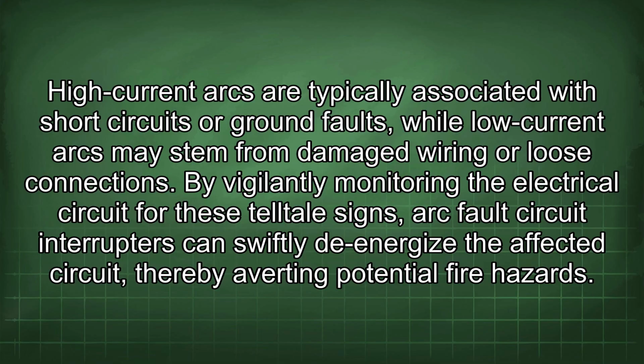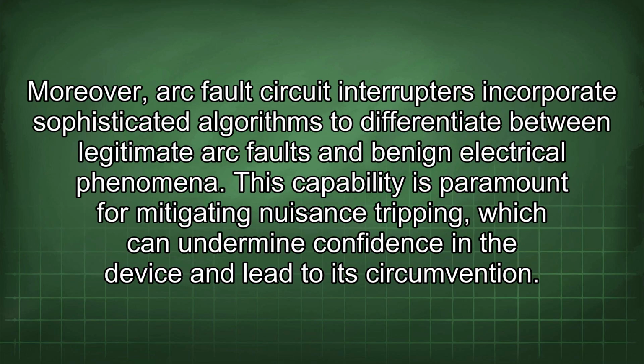By vigilantly monitoring the electrical circuit for these telltale signs, arc fault circuit interrupters can swiftly de-energize the affected circuit, thereby averting potential fire hazards. Moreover, arc fault circuit interrupters incorporate sophisticated algorithms to differentiate between legitimate arc faults and benign electrical phenomena. This capability is paramount for mitigating nuisance tripping, which can undermine confidence in the device and lead to its circumvention.